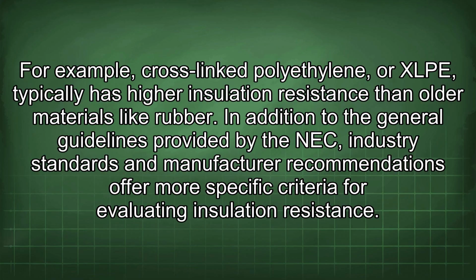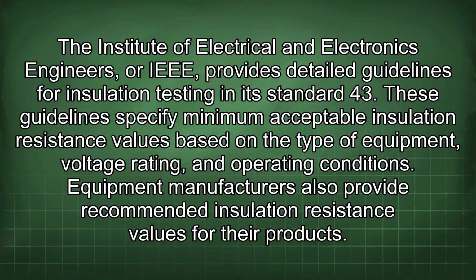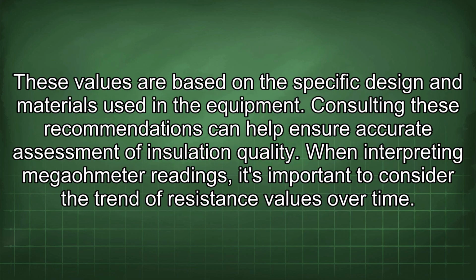In addition to the general guidelines provided by the NEC, industry standards and manufacturer recommendations offer more specific criteria for evaluating insulation resistance. The Institute of Electrical and Electronics Engineers, or IEEE, provides detailed guidelines for insulation testing in its Standard 43. These guidelines specify minimum acceptable insulation resistance values based on the type of equipment, voltage rating, and operating conditions. Equipment manufacturers also provide recommended insulation resistance values for their products. These values are based on the specific design and materials used in the equipment. Consulting these recommendations can help ensure accurate assessment of insulation quality.